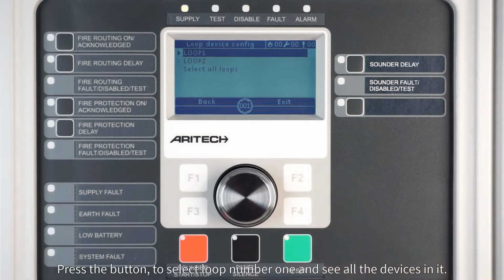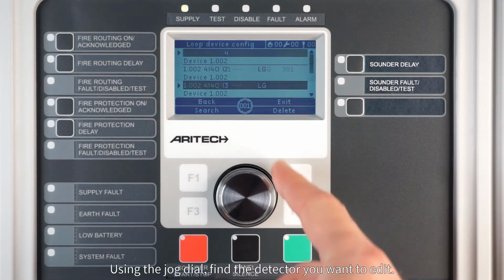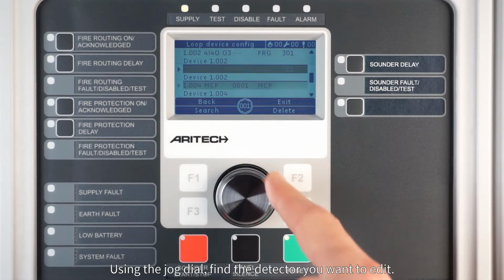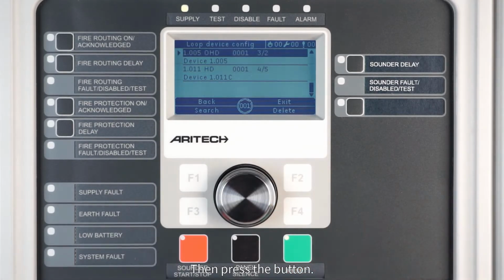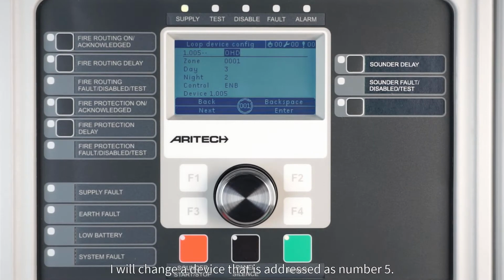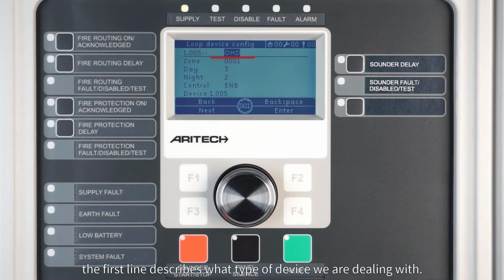Press the button to select loop number 1 and see all the devices in it. Using the jog dial, find the detector you want to edit, then press the button. I will change a device that is addressed as number 5. In loop device config, the first line describes what type of device we are dealing with. In this case it is OHD, optical and heat detector.